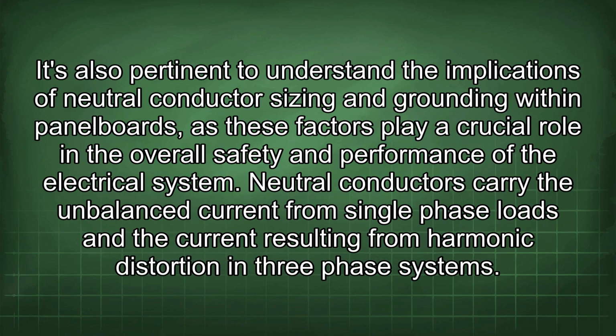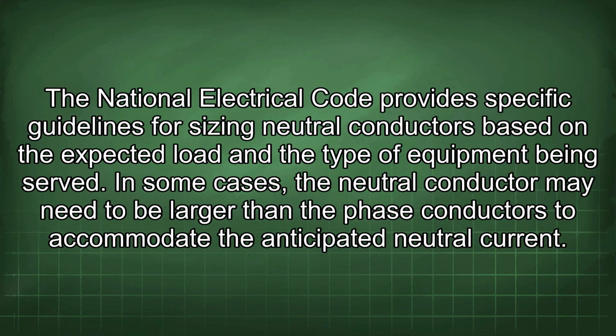It's also pertinent to understand the implications of neutral conductor sizing and grounding within panelboards, as these factors play a crucial role in the overall safety and performance of the electrical system. Neutral conductors carry the imbalanced current from single-phase loads and the current resulting from harmonic distortion in three-phase systems. The National Electrical Code provides specific guidelines for sizing neutral conductors based on the expected load and the type of equipment being served. In some cases, the neutral conductor may need to be larger than the phase conductors to accommodate the anticipated neutral current.